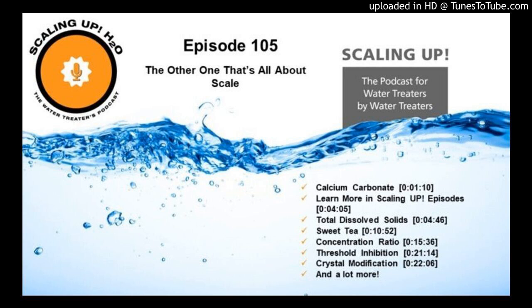Makes sense, right? And that's probably not a bad concentration ratio for most places, but what if that's what they could run and they were only running a concentration ratio of 2? Well, 1/2, if we divide that out, that would be 0.5. So if I multiply 200 by 0.5, we would be bleeding 100 gallons per minute. Folks, that's a big difference between 32 and 100 gallons, and that's wasting water.